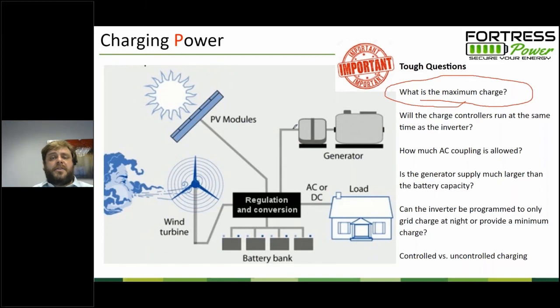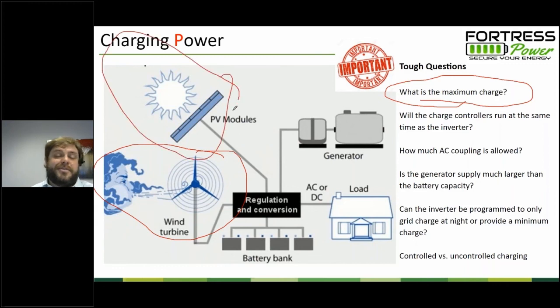And one solution to that is to throttle down the grid charge, to say the grid doesn't need to charge my batteries so quickly, so I'll dial it back. Another solution would be to program the inverter to only charge at night so that it can't conflict with when the charge controllers charge. In fact, wind, our renewable energy cousin, is a little bit more difficult to integrate into the systems because it is so unknown and unmanaged on when the wind is going to blow and how fast those bursts are going to be. Whereas with something like solar charging, you can assume that that's only going to happen during the day. You can program the grid charge to only occur at night, and that will buy you a little bit more wiggle room.